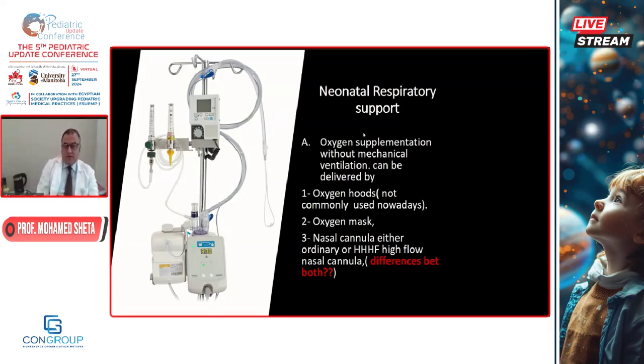Or by oxygen mask in some situations, especially in ERs, where you can find non-rebreathing oxygen masks, which can be used to support respiratory failure or respiratory distress. Nasal cannula, either ordinary or high flow. High flow is called HHHFNC, humidified heated high flow nasal cannula. The difference between both: with the oxygen nasal cannula, low flow is a maximum of 2 to 3 liters per minute, and more than 3 liters is high flow nasal cannula, which should be heated and humidified. So a warmer should be there and a humidifier should be there.